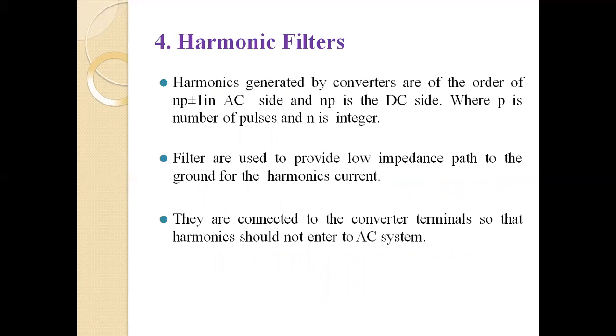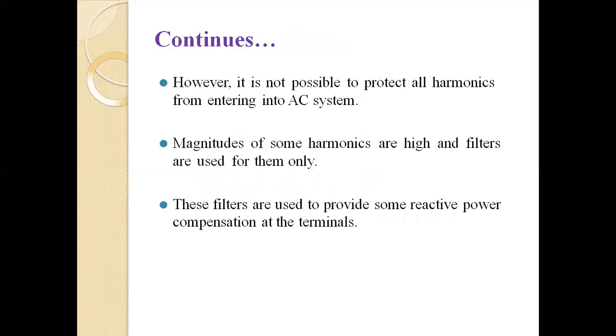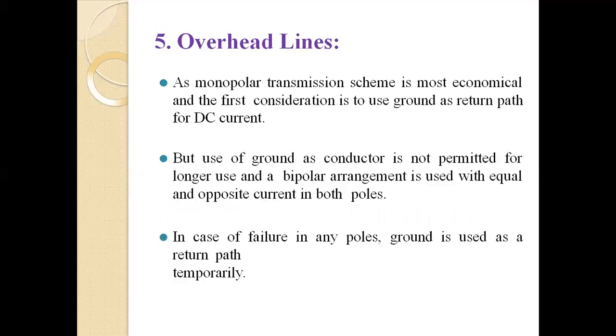Harmonics generated by the converter are of the order of NP plus or minus 1 on the AC side and NP on the DC side, where P is the number of pulses and N is an integer. Filters are used to provide a low impedance path to the ground for harmonic current. They are connected to the converter terminals so that the harmonics do not enter the AC system. However, it is not possible to prevent all harmonics from entering the AC system. The magnitude of some harmonics is high and the filters are used for them only. These filters also provide some reactive power compensation at the terminal.